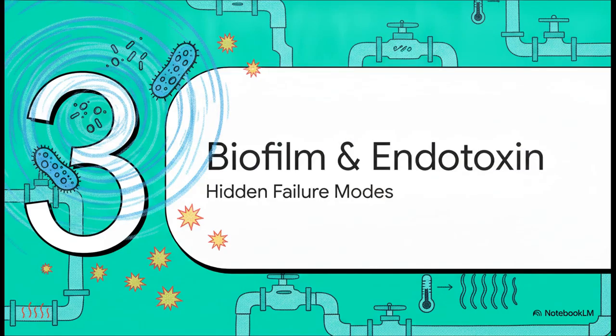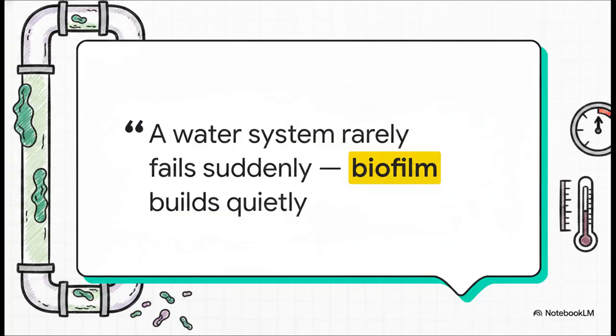Which leads us perfectly into Section 3, biofilm and endotoxin control. You might be wondering, why are those thermal controls so incredibly essential? Well, it's because a water system rarely fails suddenly. You're almost never going to get a loud, blaring alarm that just goes off out of nowhere to tell you something's wrong. Instead, biofilm builds up quietly on the wetted surfaces over time. It establishes a matrix, it grows, and it gradually sheds organisms and endotoxins directly into your water supply. Continuous flow and precise temperature controls are quite literally your primary weapons to suppress this quiet, invisible threat.